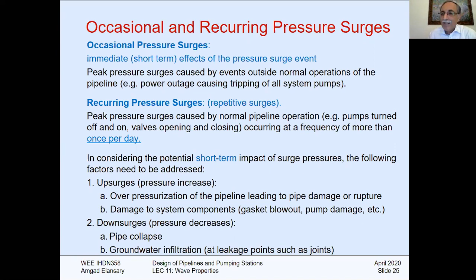Identification of peak surge. Again, this is step by step. The maximum events over the course of the pipeline design. If I'm doing a water hammer report and designing to see the maximum events, as a designer I have to look at the maximum event that will happen during the lifetime. You can ask me about lifetime: yes, you're going to simulate that. You can imitate that. You can design the lifetime of this pipe, and then look for everything that can possibly happen to it.